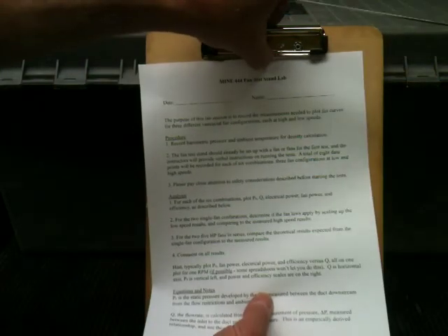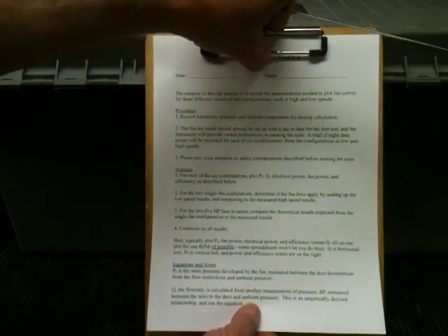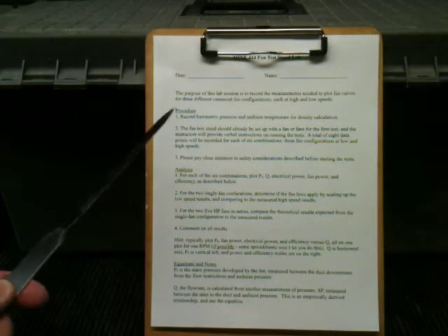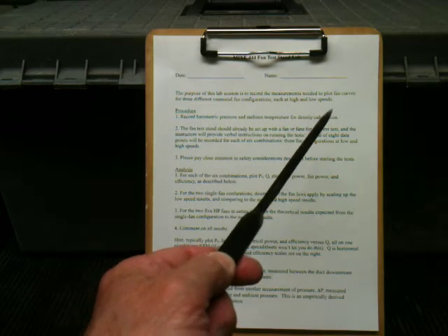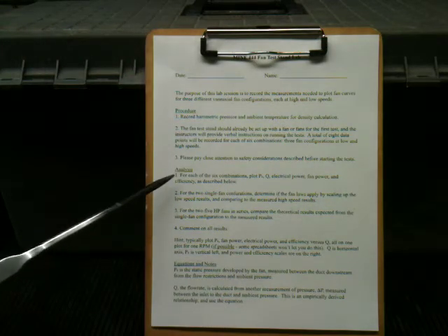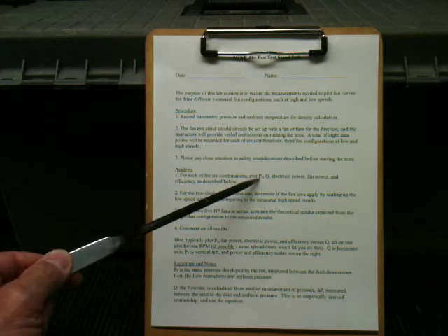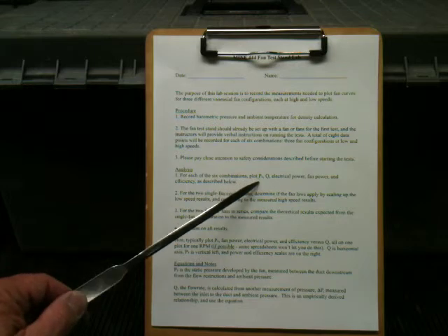So now I'm going to go back to the first page, and we will talk about the analysis of that data. Okay, so again, you will have the barometric pressure and the temperature, so calculate the density in pounds per cubic foot. You're going to need that. And then for each of the 6 combinations, you're going to plot P sub S, that's the static pressure developed by the fan. That's just read directly off the data sheet.